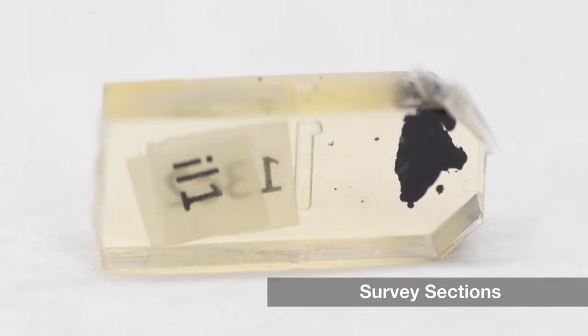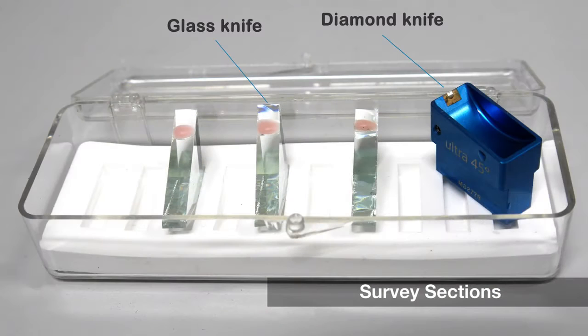Since the resin is very hard, sections can only be cut using glass or diamond knives. A glass knife is made from a strip of glass. First, a square is cut, then scored and fractured diagonally into 2 triangular glass knives.